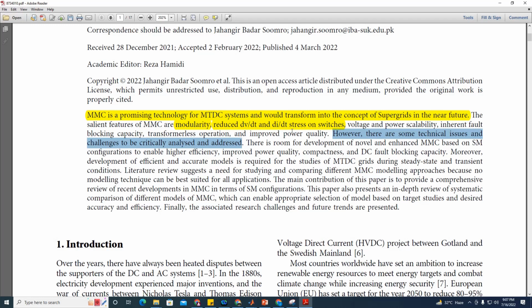One technical issue is circulating current. In MMC, circulating current flows, and it basically consists of two components. One is a DC component, IDC by 3, which is desired and required. But the AC component, at twice the fundamental frequency, needs to be eradicated, because if this circulating current is not suppressed, it will trigger further problems.